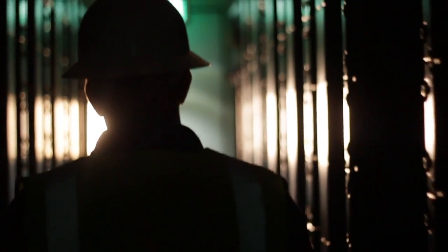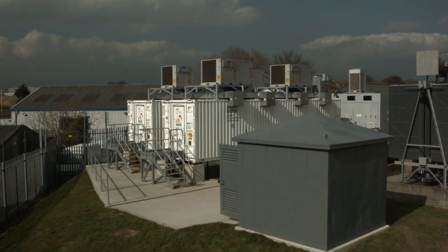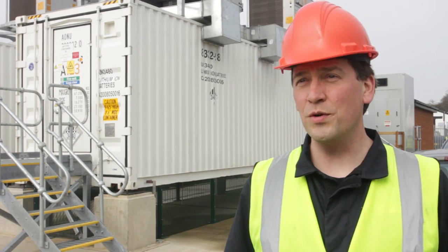The rating of the system is 2.5 megawatts source and sink, and 5 megawatt hours, so we can push and pull quite a bit of power onto the mains. 2.5 megawatts is approximately enough to drive 500 very large homes for several hours. In our urban test cell at 6,000 volts — traditionally at the lower end of our distribution network voltage level — the currents are relatively high, so the energy storage in this instance is enabling us to limit the amount of current being passed through that transformer by supporting it thermally.